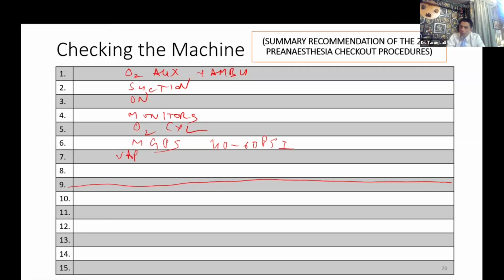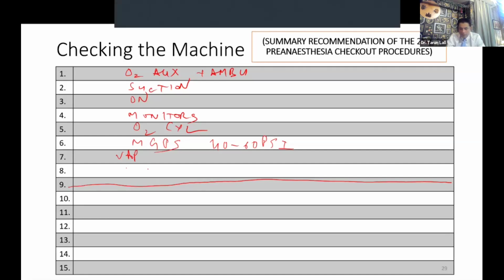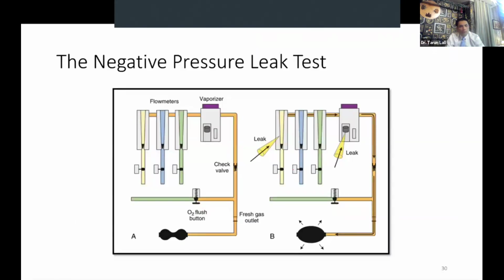So once I have checked the vaporizers, then I see whether the flow control knobs are able to deliver the gases fully. And I also check for the negative pressure leak test. Now, a word about the negative pressure leak test. What we see here is that in the modern machines, you have this check valve, which is downstream of the vaporizer. The purpose of this check valve is that it prevents back pressure from damaging the sensitive equipment. But it also means that if I am using positive pressure to check for a leak, then that positive pressure will be able to check only up till this stage, because beyond that, the positive pressure is not transmitted.